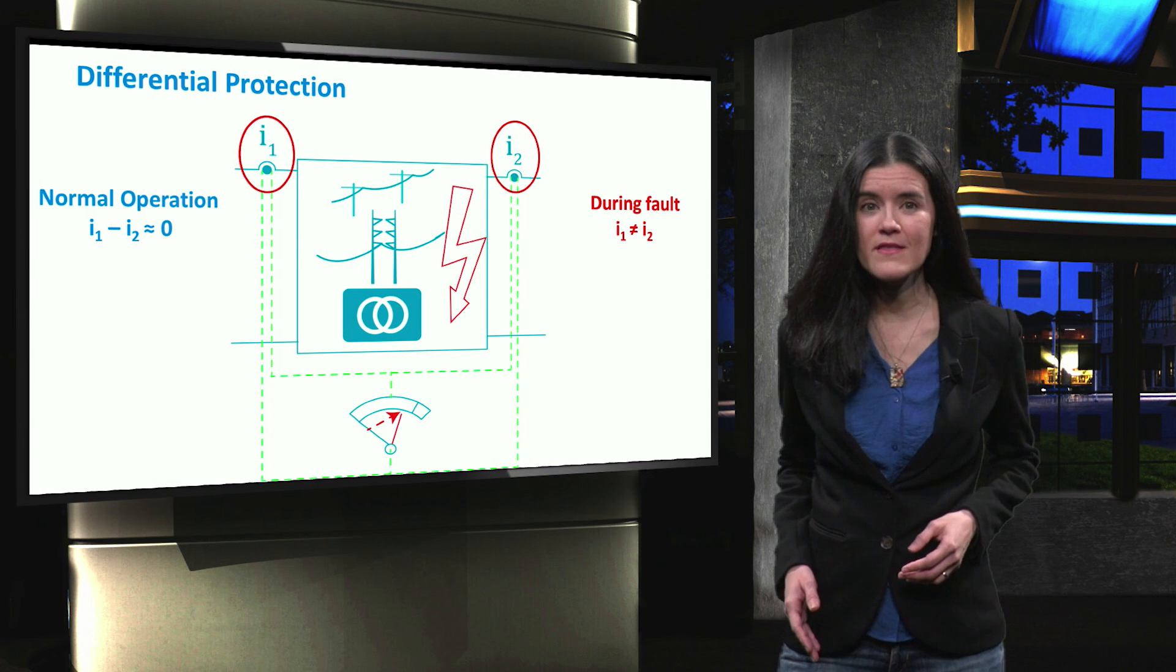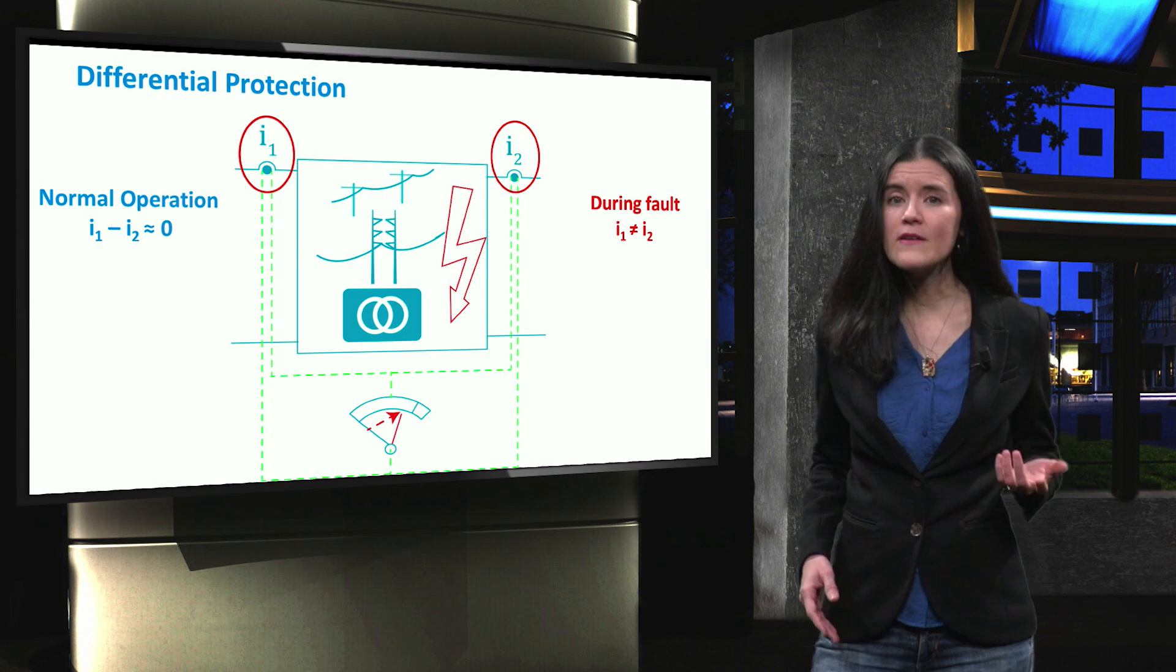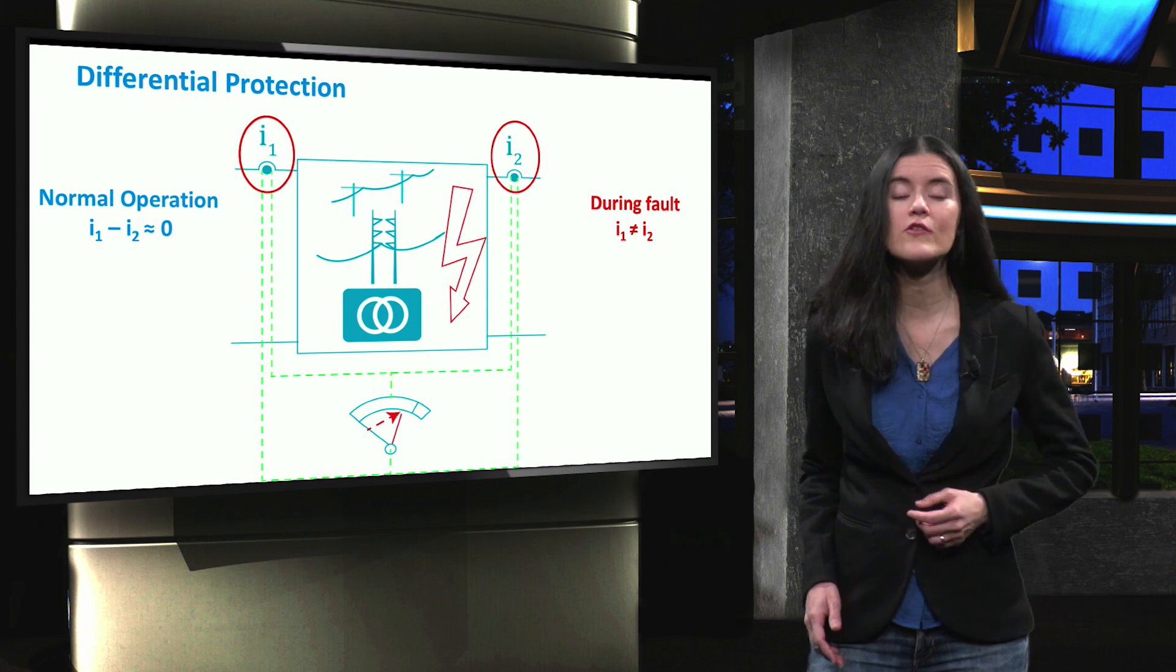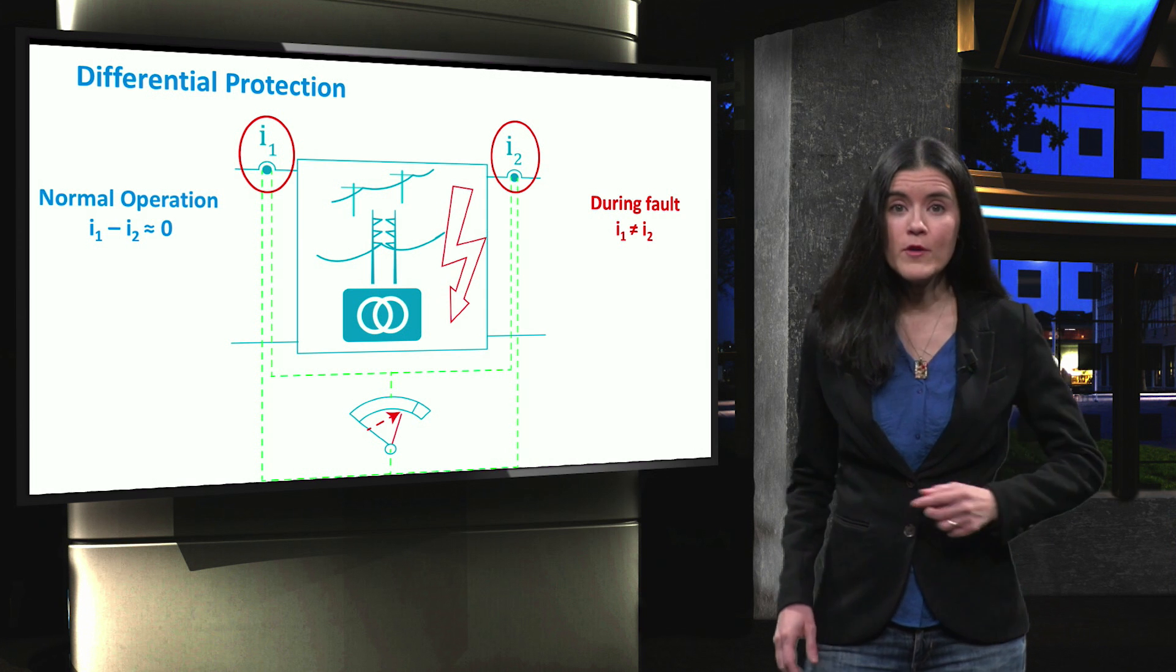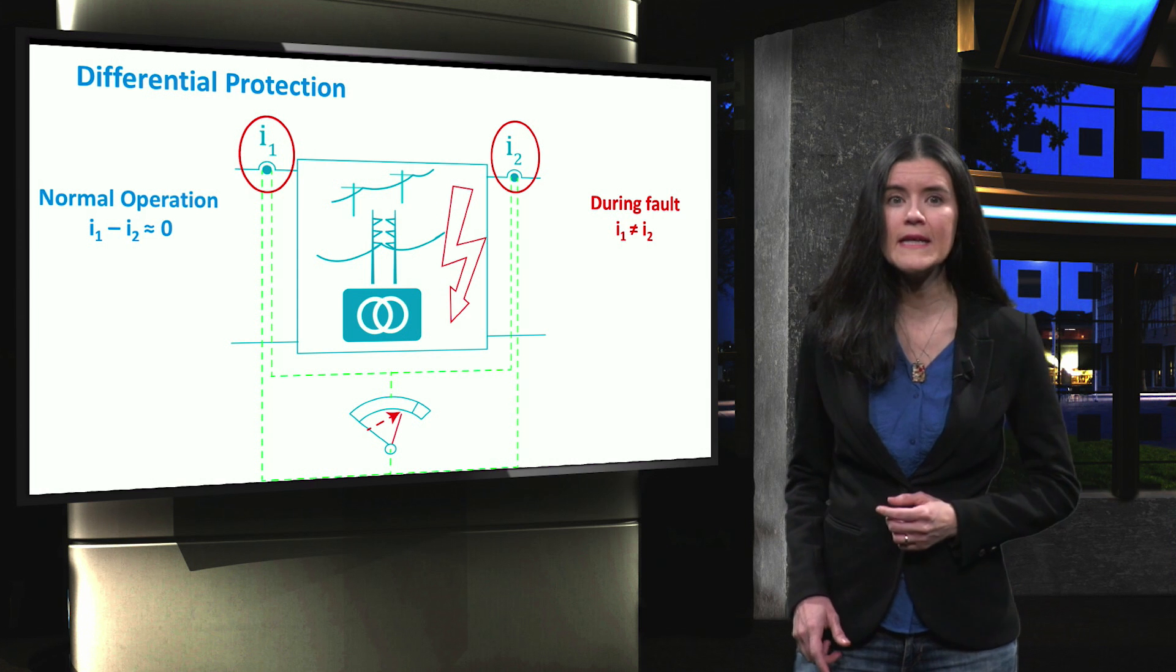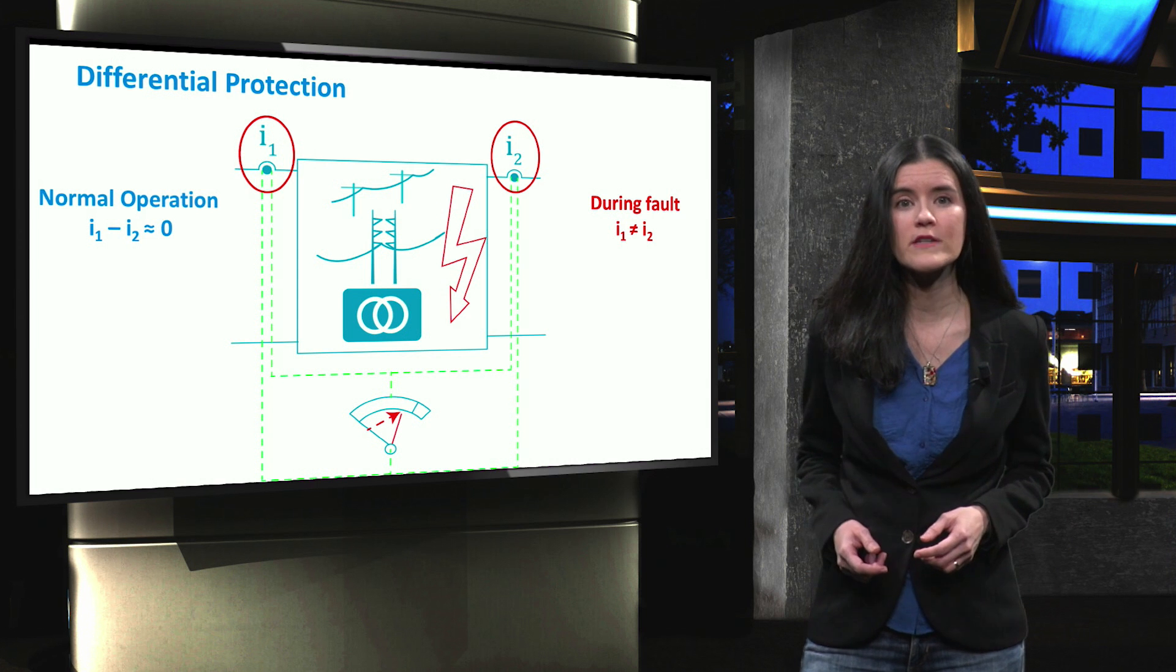Although this protection method has high selectivity, it relies on the communication network to transmit the measured currents to the control logic. As the communication network is also subject to failures, a backup protection is usually needed in addition to the differential protection, causing a great increase in the cost of this method.